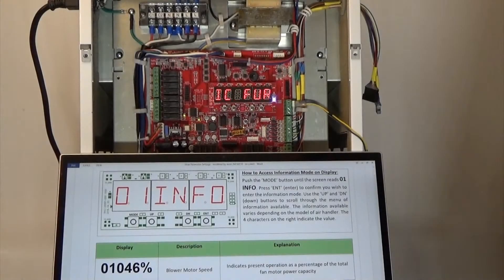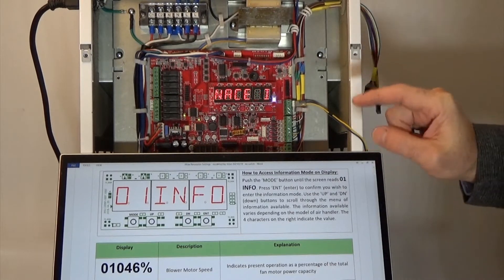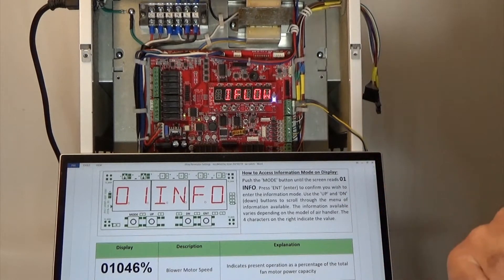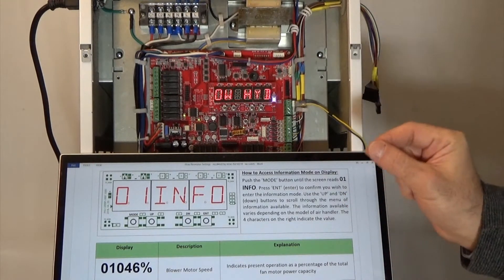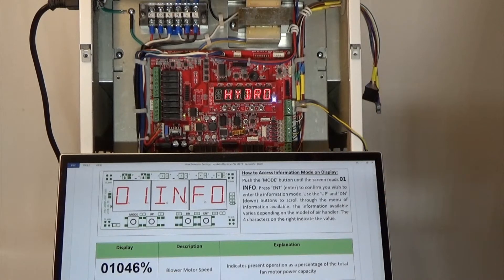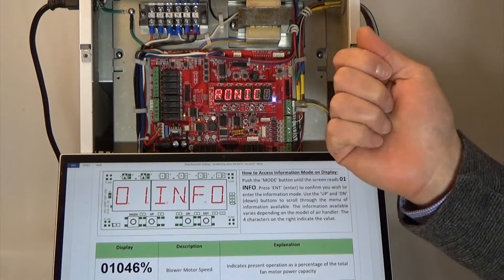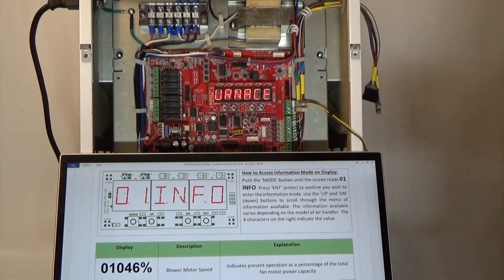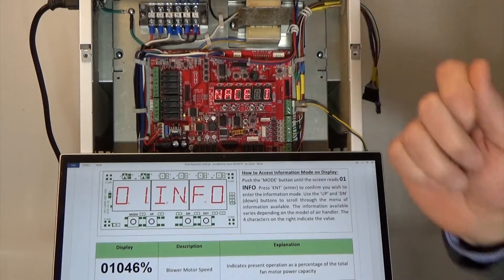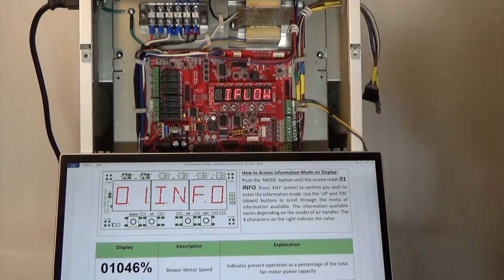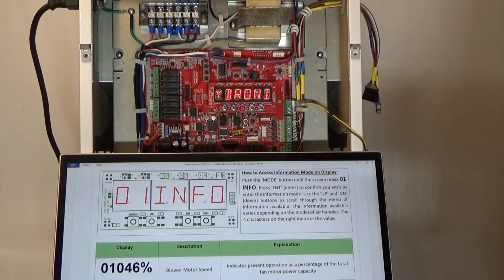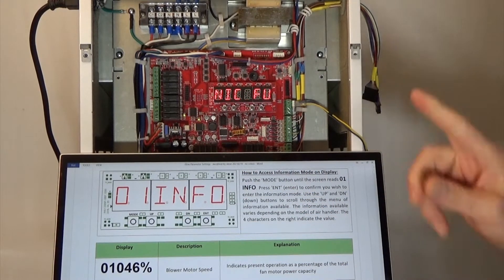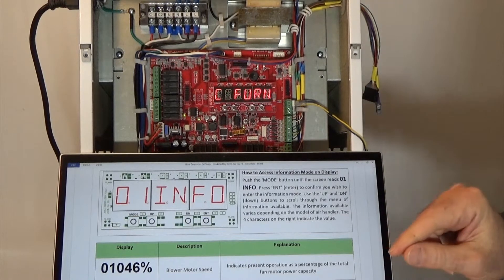Hi, this is Steve. In this segment we're going to look at the information mode. The information mode will tell us all about the present state of the unit — what it's seeing in terms of incoming water temperature, outgoing water temperature, return air temperature, supply air temperature, outdoor temperature, and the condition of all the relays and the damper positions. So let's scroll through that quickly.